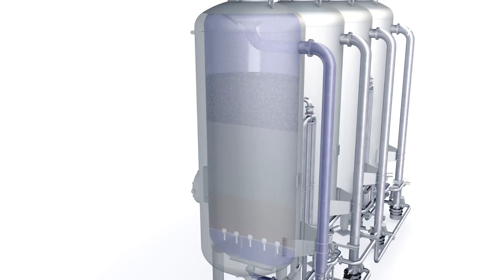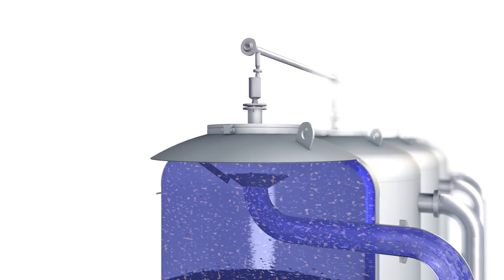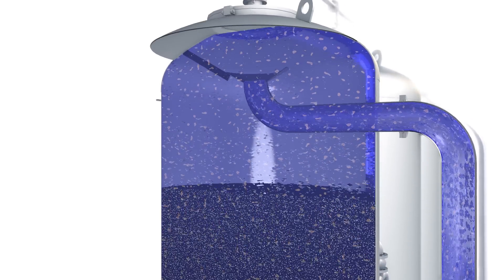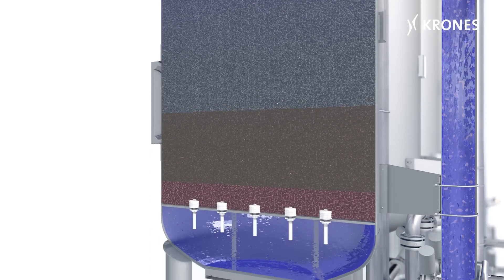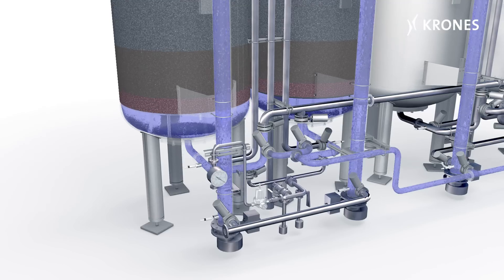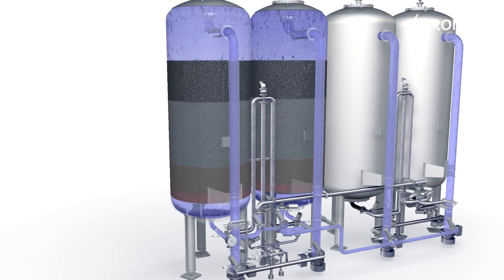The mains water flows into the first tank. Filtering materials in the multi-layered filter are differently arranged, so that several undissolved substances can be removed simultaneously, top to bottom, in line with the principle of pre-coating filtration. The mains water flows through the filtering layer in each tank, and the particles arrested are deposited on the filtering medium. The same thing happens simultaneously in the second multi-layered filter.